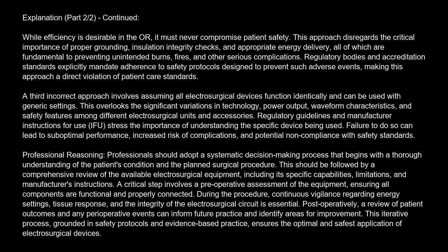Professional reasoning. Professionals should adopt a systematic decision-making process that begins with a thorough understanding of the patient's condition and the planned surgical procedure. This should be followed by a comprehensive review of the available electrosurgical equipment, including its specific capabilities, limitations, and manufacturer's instructions. A critical step involves a preoperative assessment of the equipment, ensuring all components are functional and properly connected.